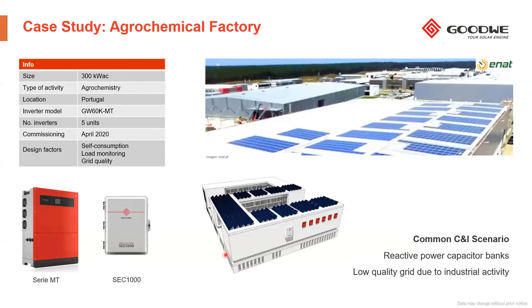This is something that we need to consider when we design a PV plant in this kind of scenario, in this kind of facilities. Our solution is the SEC 1000. Let me introduce this solution. It's a device that gives us a lot of possibilities in this kind of scenario. For instance, to monitor up to 60 inverters. And I have to say, not necessarily the same inverters. We can combine SDT generation 2 with different models, with MT or different SMTs, etc., as long as all of them communicate with 485. So we can combine all the GoodWe commercial and industrial inverter portfolio with one device, up to 60 inverters, right?